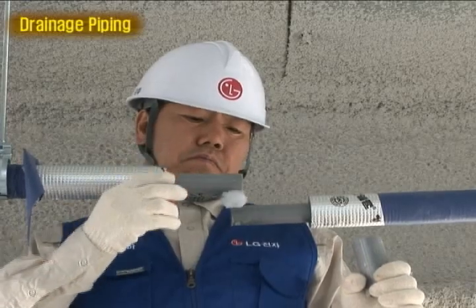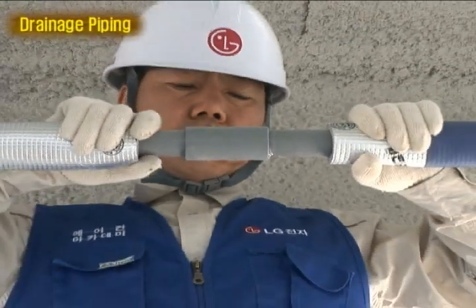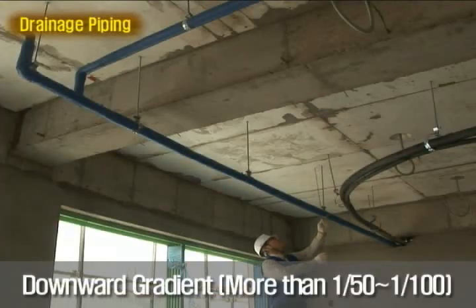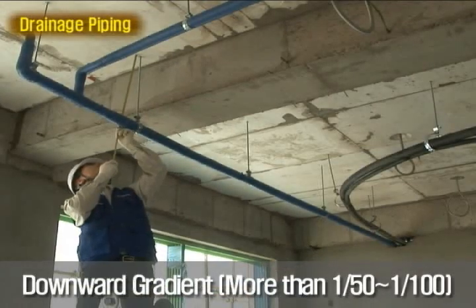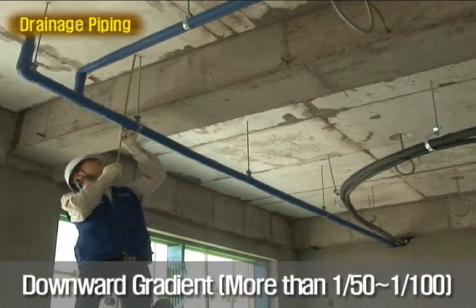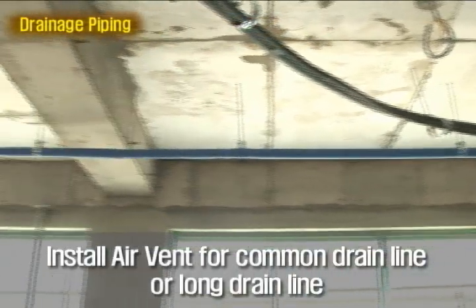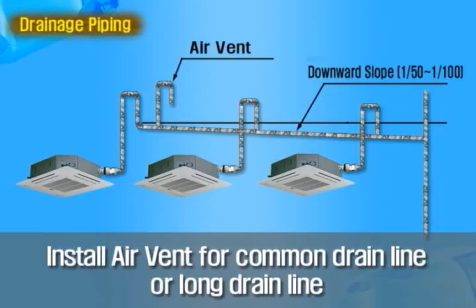When extending drain pipe, use extension socket and adhesive not to make a leakage. For an easy water flow, arrange a downward gradient of more than 1/50th to 1/100th. Install an air vent for a common drain line or a long drain line to make a good water flow by the pressure difference.